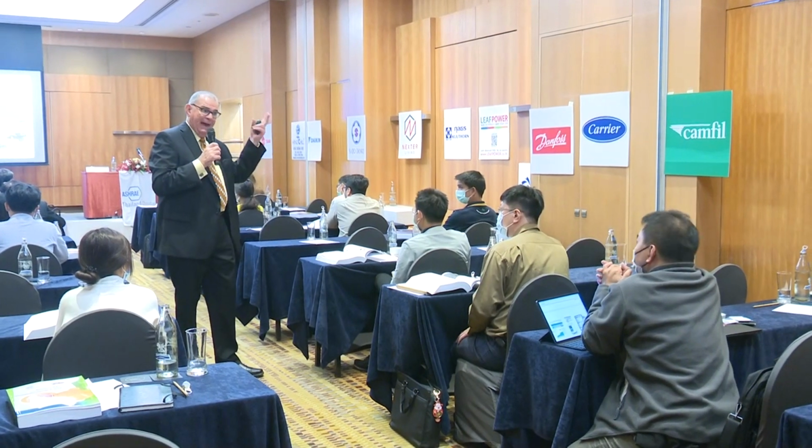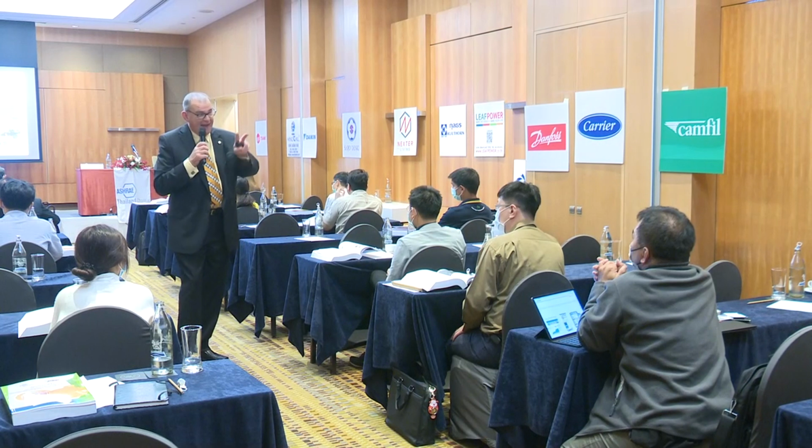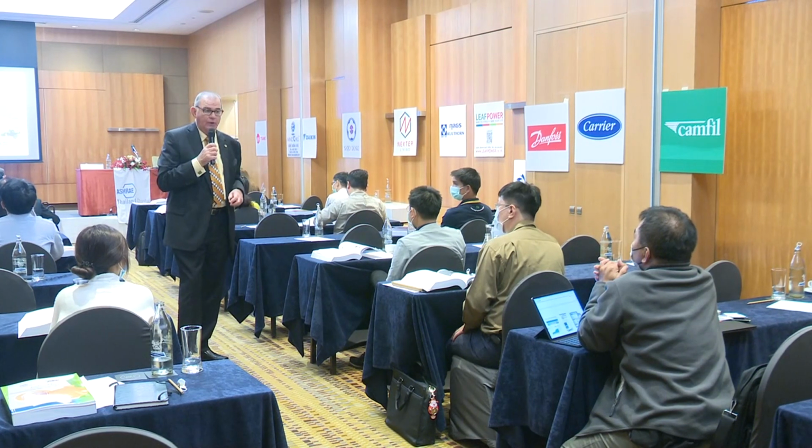So the reason you know it's correct is because we are now calibrating it installed. Previously, it's calibrated at the factory in a laboratory, and that's under perfect conditions. Now you get in a job and it's not perfect anymore. So we use our instruments to calibrate it as it is installed in the system. So that's how you know that it's actually installed and operating correctly and the calibration is correct.